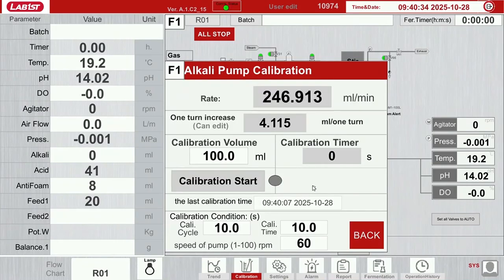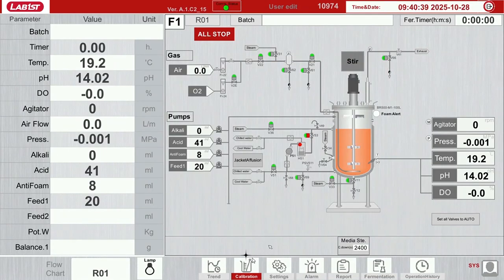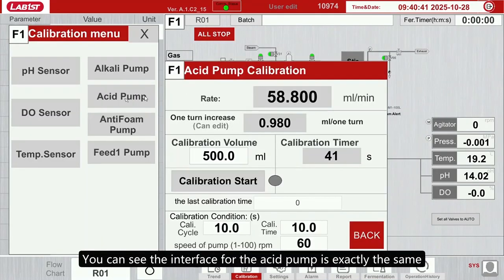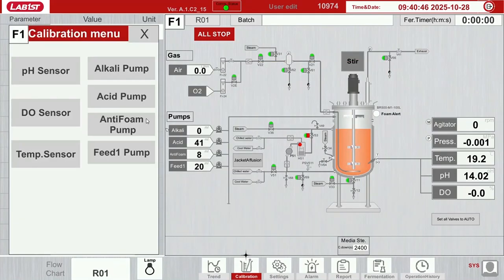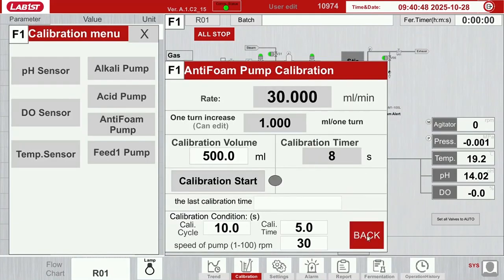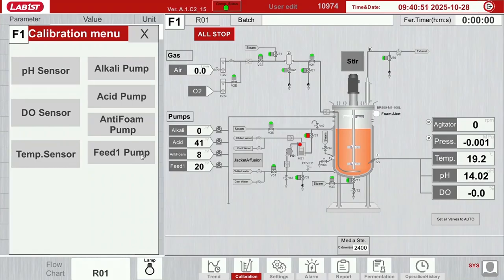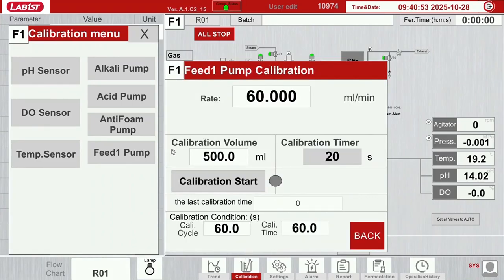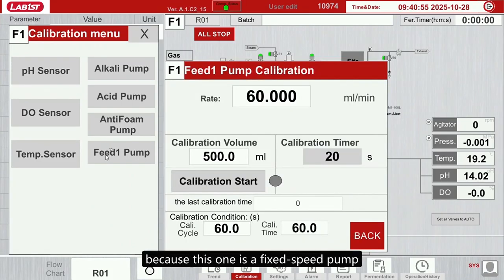This is the alkali pump. You can see the interface for the acid pump is exactly the same. For the feed pump, because this one is a fixed speed pump, its coefficient won't display. It uses a built-in fixed speed for rotation, for calibration.